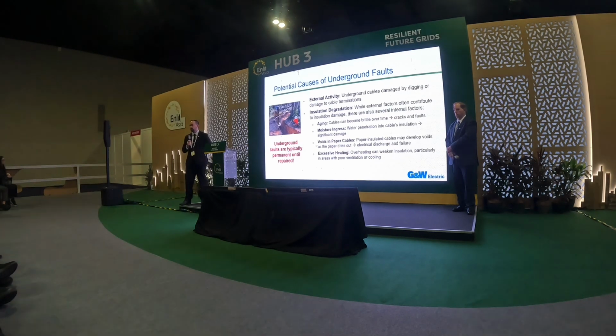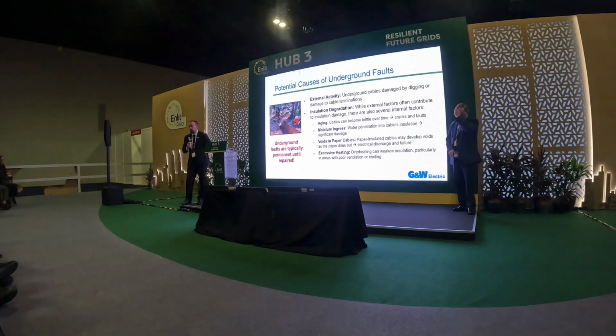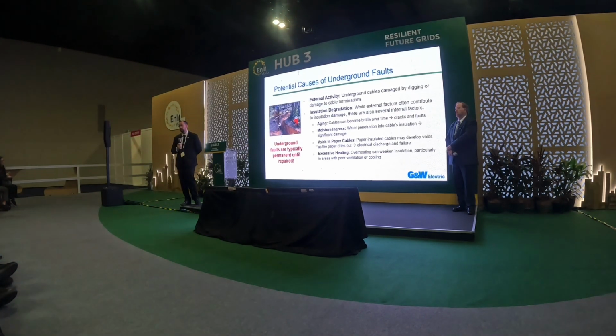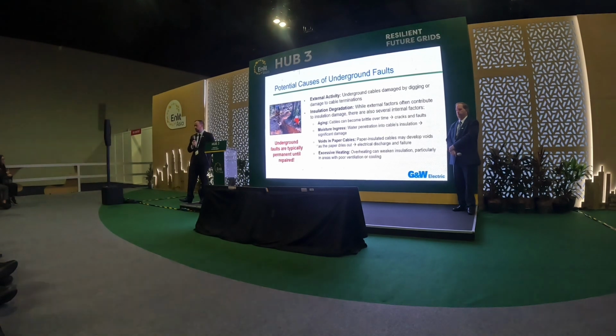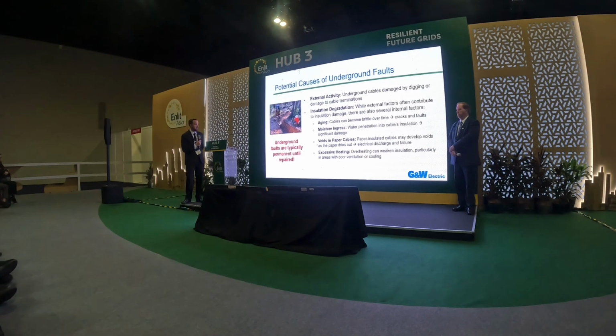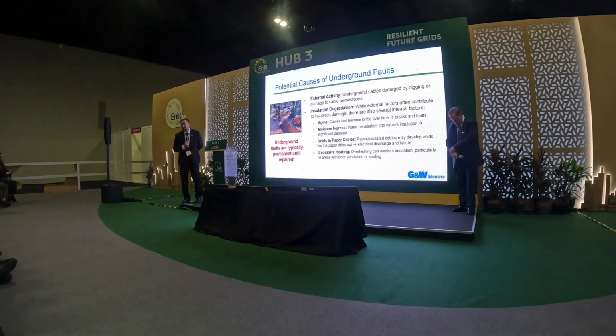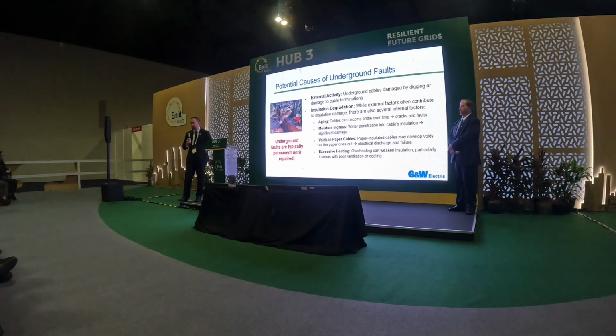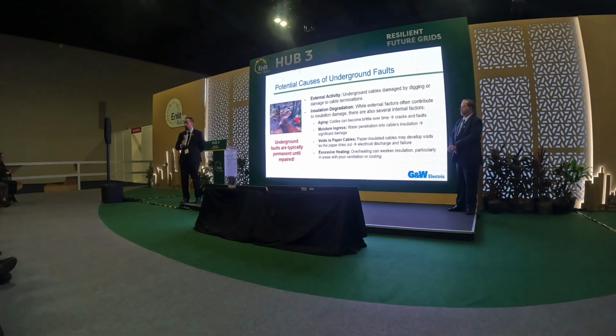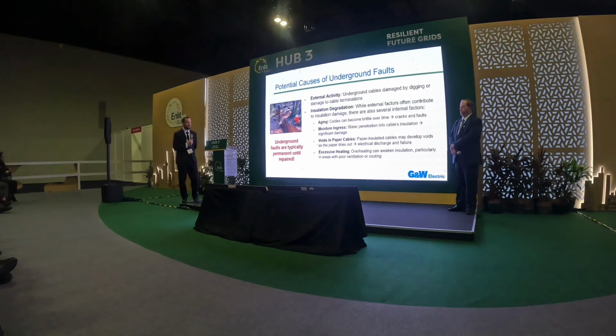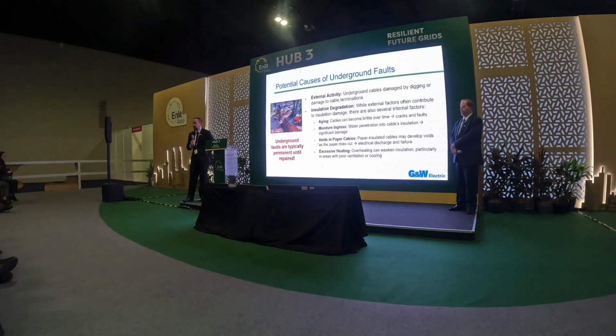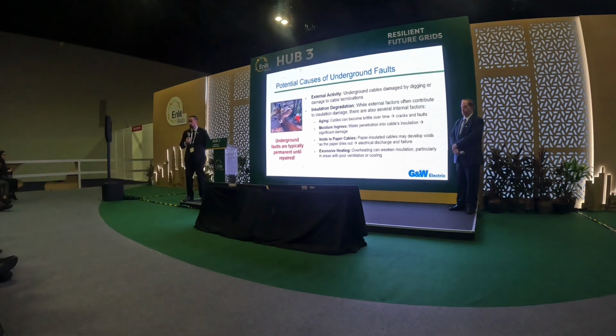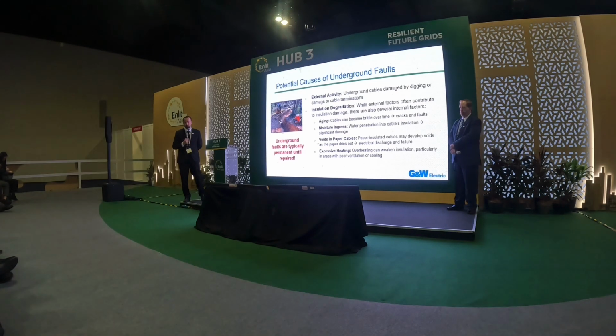On older transmission systems, paper insulated cables, there's still plenty of that installed. I know in North America, one of our main markets. But as that paper dries out over time, it's typically impregnated with a fluid and oil. And as that paper dries out, it can create voids which can cause discharges and failures of that cable.